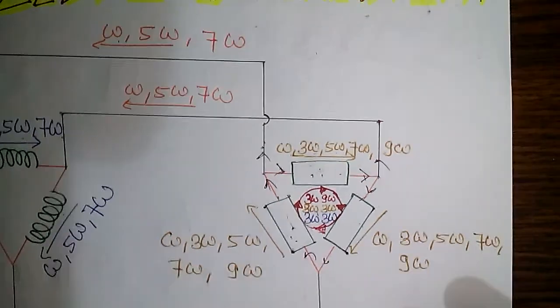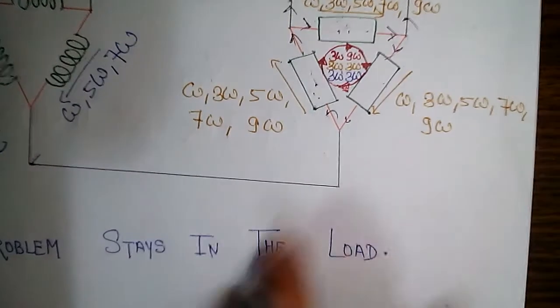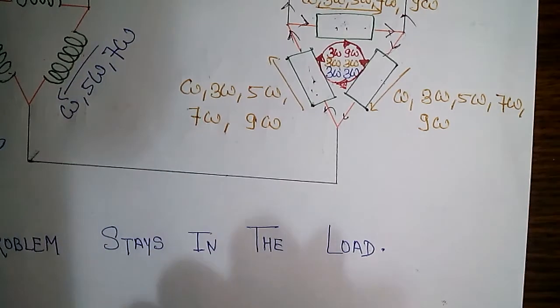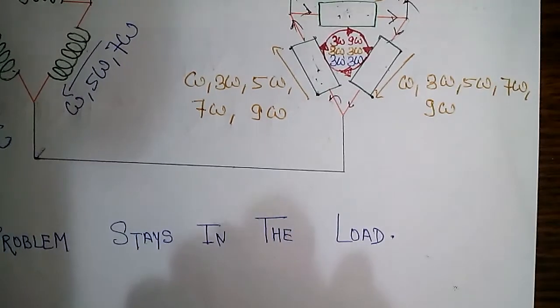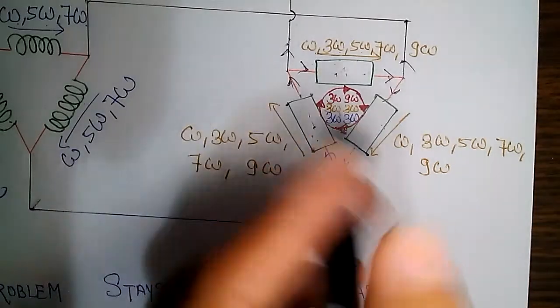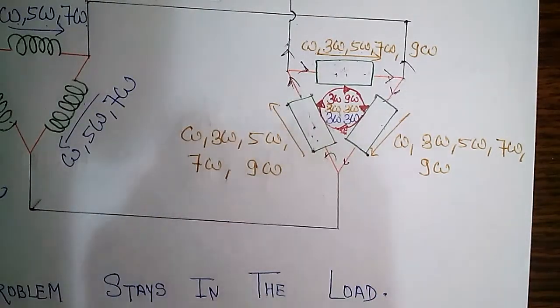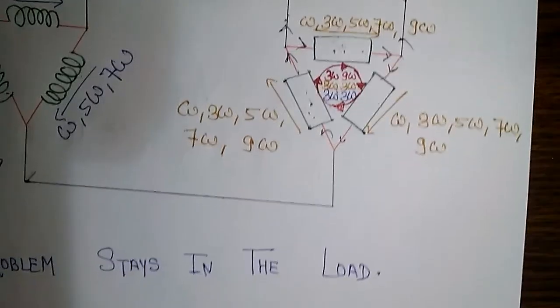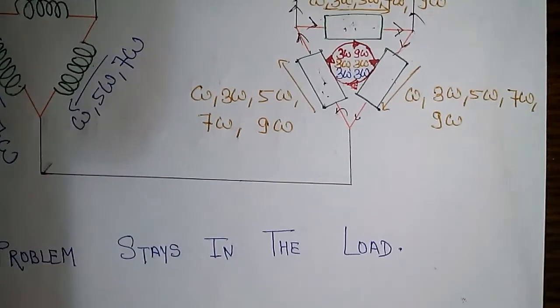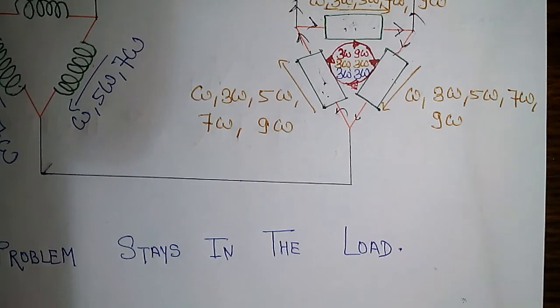Ultimately they will not cause any problem in the line — the problem due to third harmonics stays in the load. If you have a delta-connected transformer, it may heat up because the third harmonic current will be revolving in the windings only. So the problem stays in the load. I hope you got a better understanding of this. If you have any queries regarding harmonics please comment, and please subscribe to our channel and share our videos. Thank you so much.